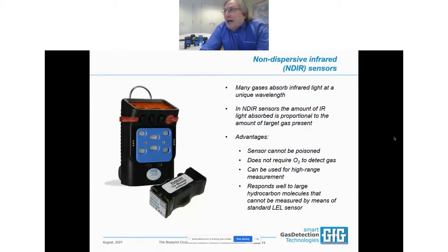We have a lot of proprietary technology in our products, including our patented unique infrared LEL, infrared CO2, and combination IR LEL, IR CO2 sensors. Now, one of the things you'll notice right away is it is bigger than the other sensors. And this is a case where size matters. On the inside of the sensor, we shine a beam of infrared light across a sensing chamber. And molecules that you're trying to measure absorb a little bit of that light. So you start out with more light than you wind up with because some of it has been absorbed.